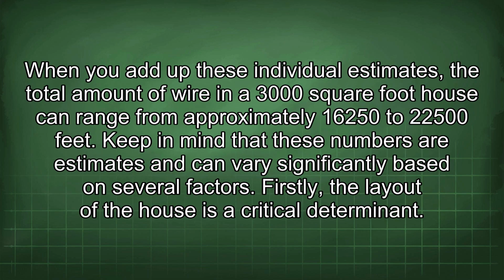When you add up these individual estimates, the total amount of wire in a 3,000 square foot house can range from approximately 16,250 to 22,500 feet. Keep in mind that these numbers are estimates and can vary significantly based on several factors.